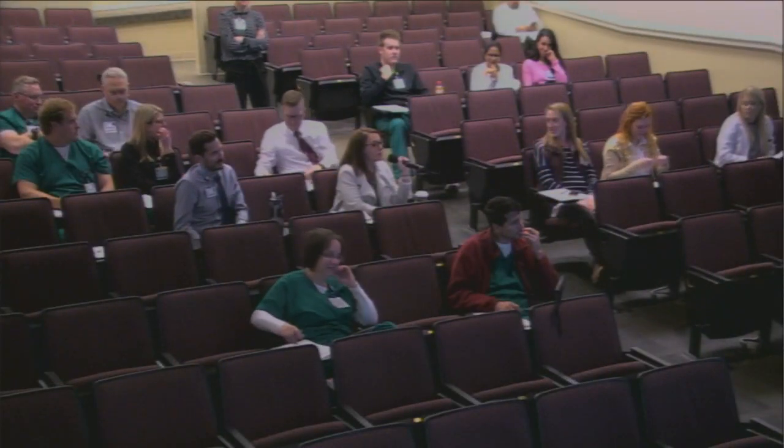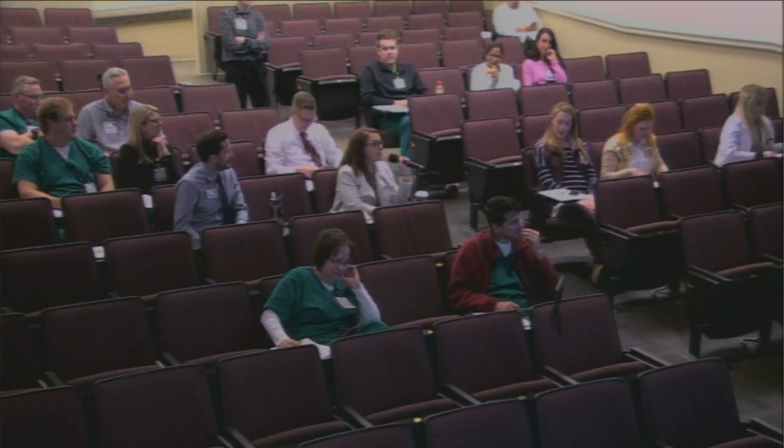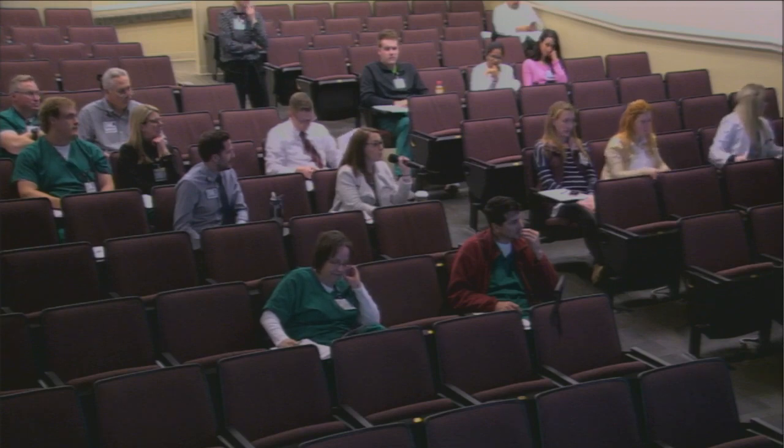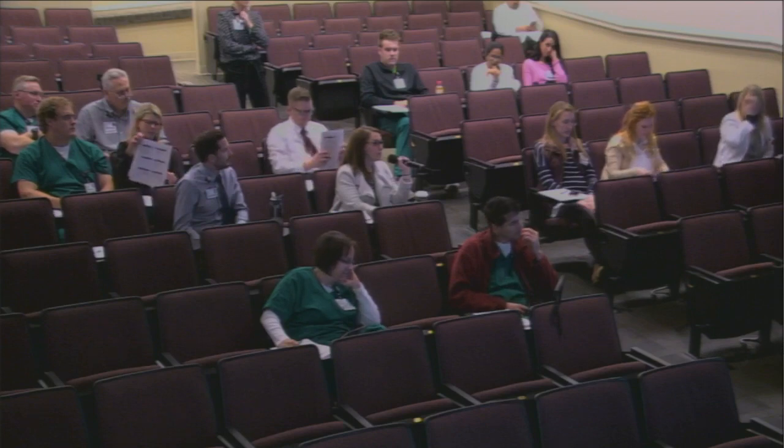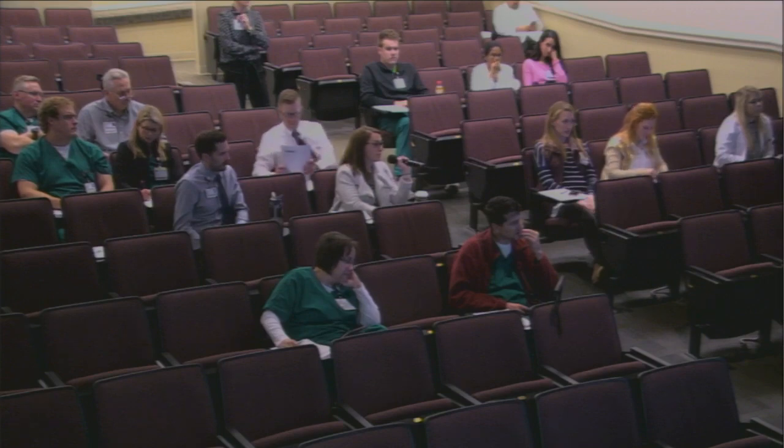Anybody else? Thank you. Ooh. I feel fancy. So in calculating the effluent dose, is there any significance in patients who are morbidly obese in terms of what weight you should use to calculate their effluent dose? And is what we should use the same thing that will pull in for the nurses when they're calculating the effluent dose? So the machine calculates the effluent dose on the machine, and they are to use the patient's actual body weight. So you should always use the patient's actual body weight. Thanks. Yep.